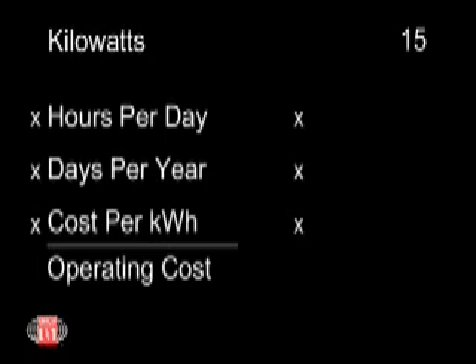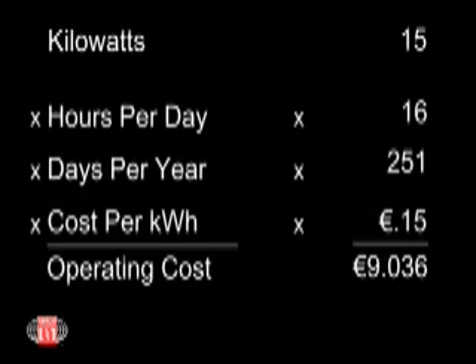Here is the formula for calculating the operating cost of a fan. For example, assume a fan with motor consuming 15 kilowatts running 16 hours per day for 251 days per year. At 0.15 euros per kilowatt hour, the cost of running that fan is approximately 9,000 euros per year. If we increase the speed 10% to compensate for system effect, our new operating cost is nearly 12,000 euros, which is an increase of approximately 3,000 euros per year. And that is just for the system effect that impacts the inlet side of the fan.